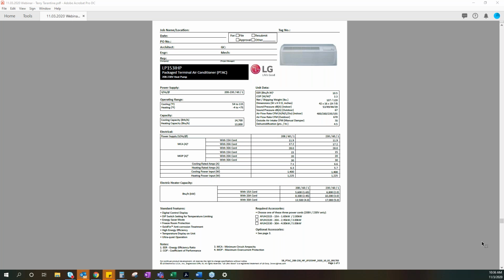And if you notice, they also have a manual intake air damper. So now we can also lower our cost of running, lower our sound levels, and introduce the fresh air that more codes are requiring. So this new unit is very exciting for us. It's something that we'll be working with the utility companies to incentivize changeover, because this is one area where we can gain significant energy advantages.